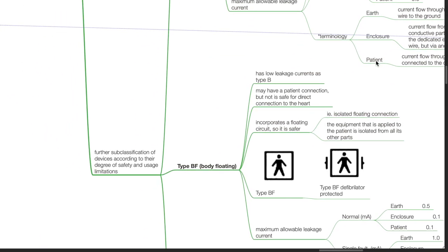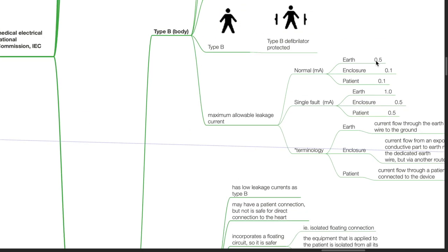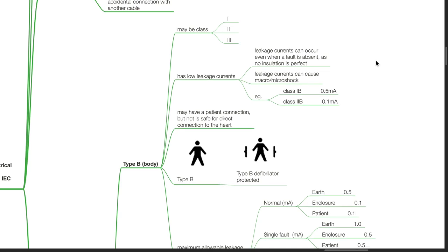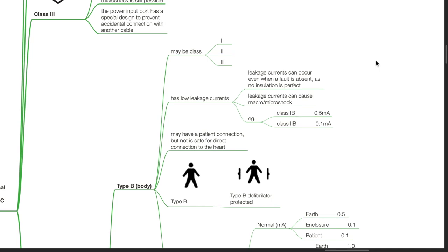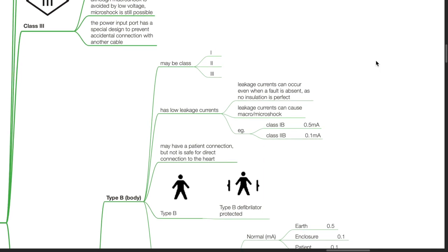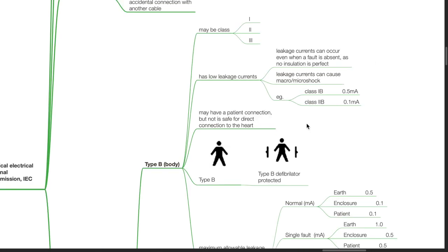Further subclassification of devices according to their degree of safety and usage limitations. Type B may be class 1, 2, or 3. These equipments have low leakage currents. Leakage currents can occur even when a fault is absent, as no insulation is perfect. Leakage currents can cause macro or microshock.